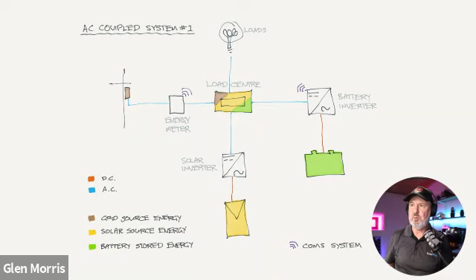That means it can parallel with the grid on the left-hand side of the picture. Because it can parallel with the grid, it needs certification and permission to connect to the grid. We have a standard for inverters that connect to the grid, AS4777.2, which is a safety and performance standard for any inverter that parallels with the grid. So this battery inverter meets the same requirements on the grid port as required for any solar inverter, because it's interacting with the grid.